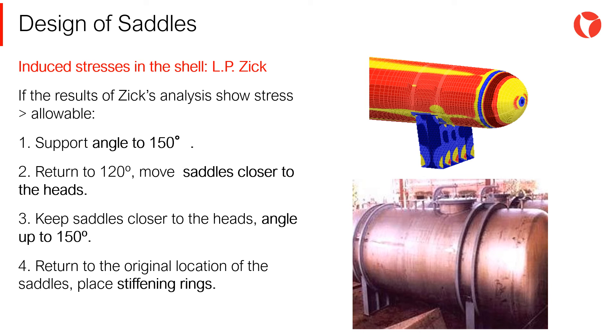If the results of the Zick analysis show that the stress level in the shell is higher than the allowable, good practices to solve this situation are the following: increase the support angle to 150 degrees; return to a 120-degree design and move the saddles closer to the heads, using the stiffness provided by the heads; keep the saddles closer to the heads and increase the angle of support up to 150 degrees; or return to the original location of the saddles and place stiffening rings in the plane of the saddles.